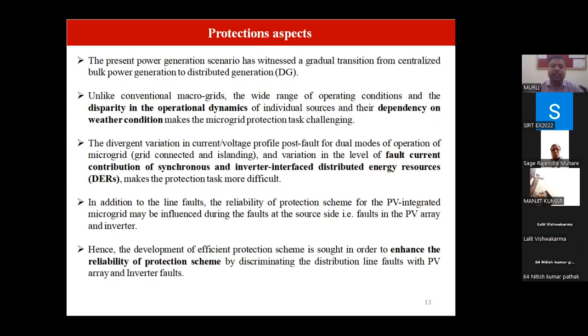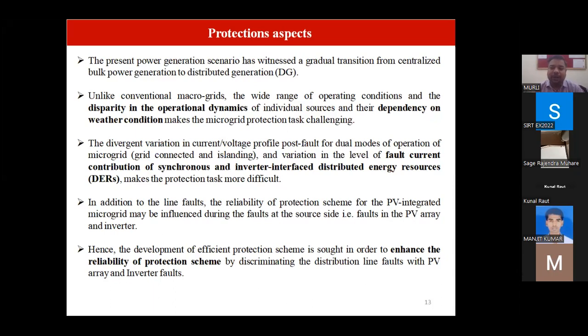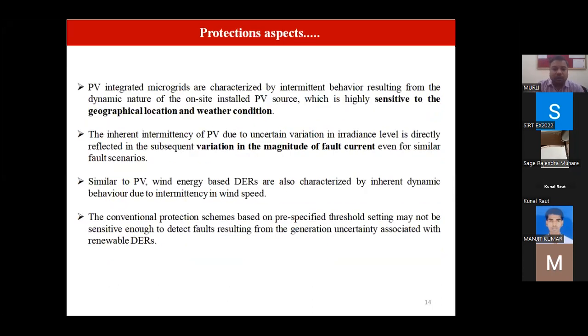So this operational dynamics also makes the protection task very challenging, because if you put a relay working on a pre-specified threshold setting, that may not work, because the operating conditions are different. So you cannot use pre-specified threshold setting based relays, overcurrent relays, or fuses or protection devices which are not dynamic. In order to pick up this dynamic behavior, we should have some adaptive technique, or you can also use machine learning based techniques.